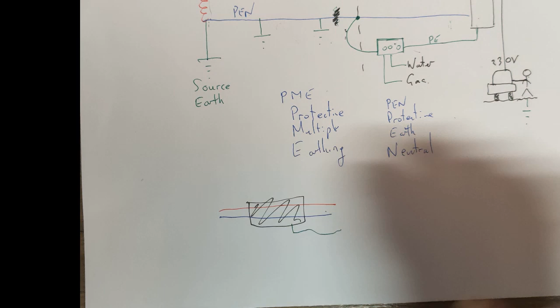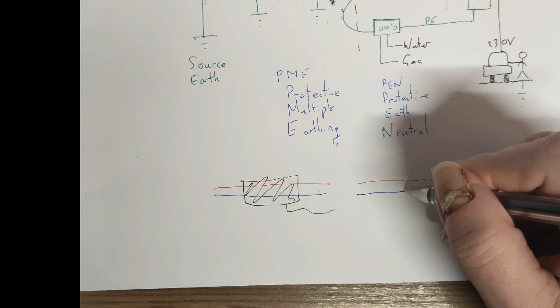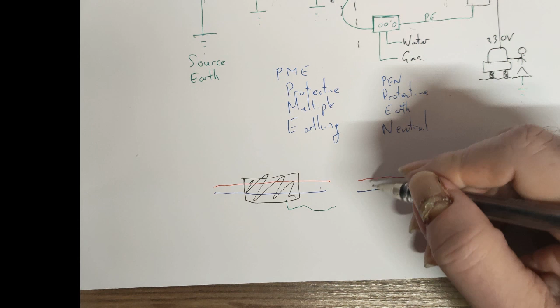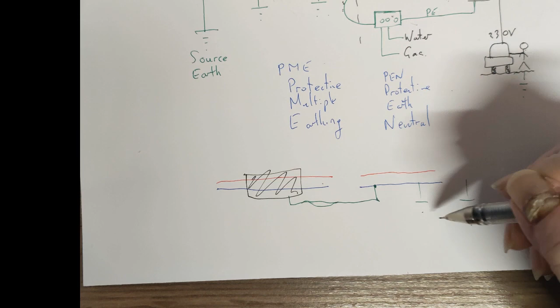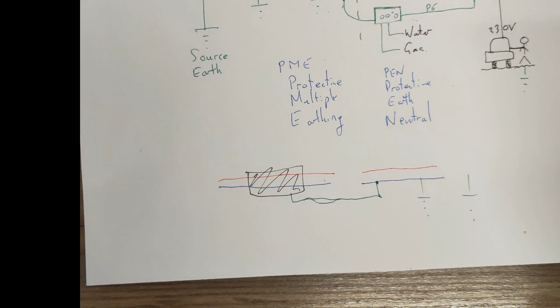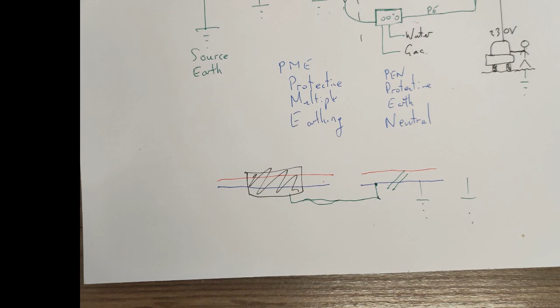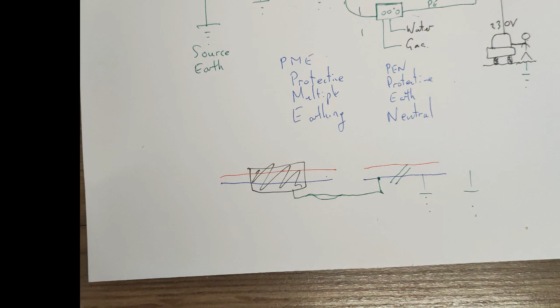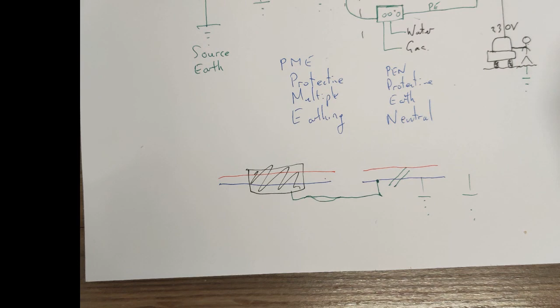Well, these days they're not going to repair that cable with one of these older type cables. They're going to replace it with one of the new ones, and they'll only have a red and a blue. So what they do is they hook your earth there, and then they put a load of earth spikes into the cable, and effectively what you've now got is a TNCS system, where it looks like it's a TNS system in your property, but it isn't, it's TNCS. If this now breaks there, you've got exactly the same problem. That's why in 722 it mandates that regardless of the system that you've got, you either don't use the earthing arrangement back to the substation, or you have something in the EV unit which will detect an open PEN fault, which is what this is called.